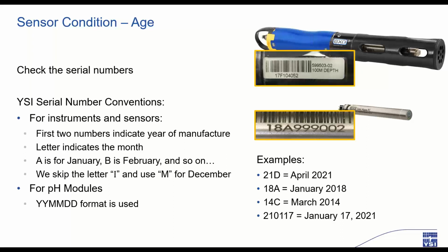We do have a few new products that are only numbers. And in this case, the first 2 numbers will be the year, the second 2 numbers the month, and the next 2 numbers the day of that month. pH modules have a lifespan of about 12 to 18 months. And that is true whether you're actively using them or not. So whether you have the pH installed or it's in the box on the shelf as a backup, that sensor is going to be using itself up, whether in storage or deployed on the sonde. Pay closer attention to a sensor that's a year old, and if it struggles during the calibration process, then make sure you've got one on hand and ready to go if you should need it.